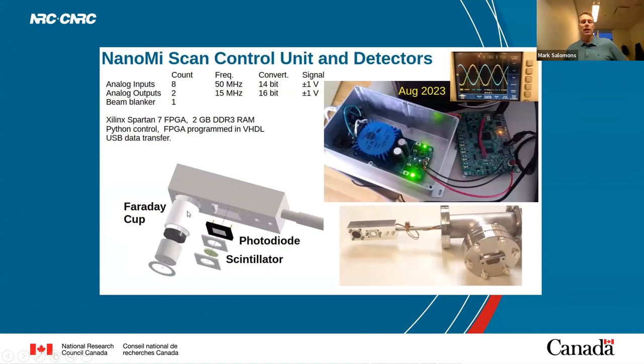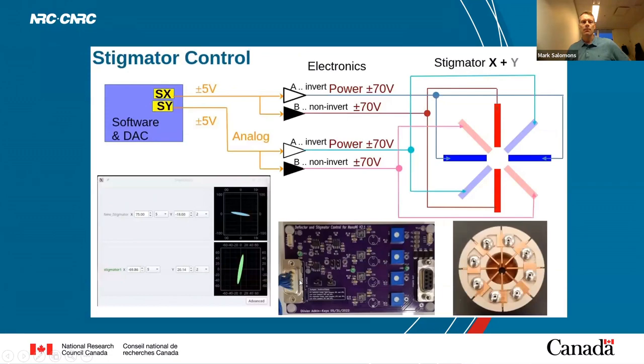In this iteration we built our own Faraday cup, which lets you determine your beam current. For our STEM we have a photodiode and a scintillator. For the eight-plate stigmator, eventually you may want to individually control the voltage to each plate, but we just have inverting and non-inverting wiring to simplify the system — you can use it to shape your beam, and always go more complex later.